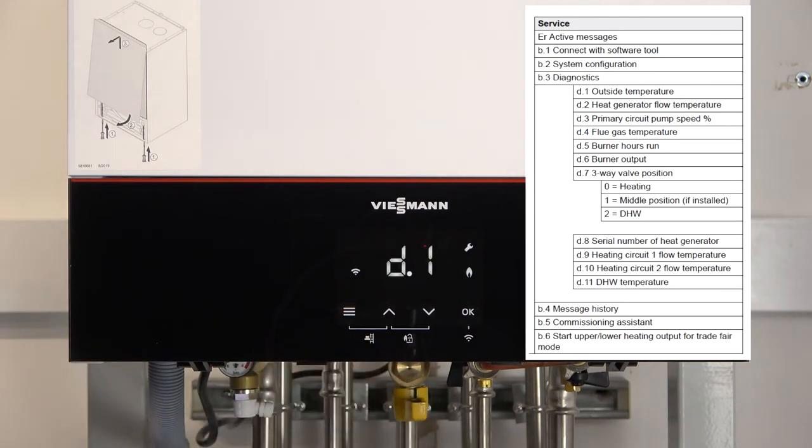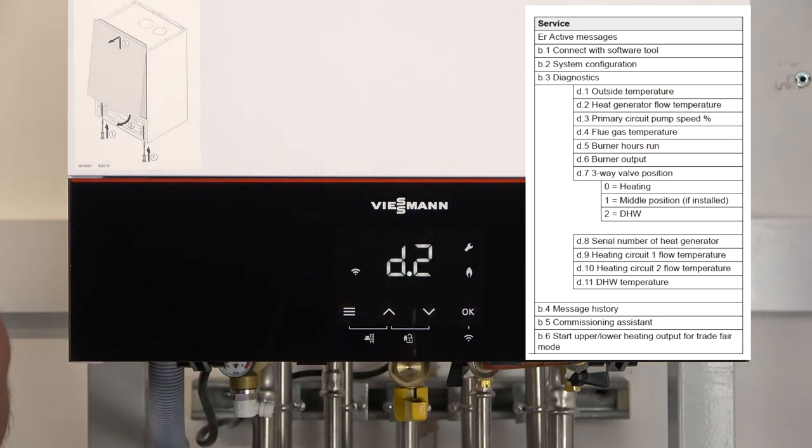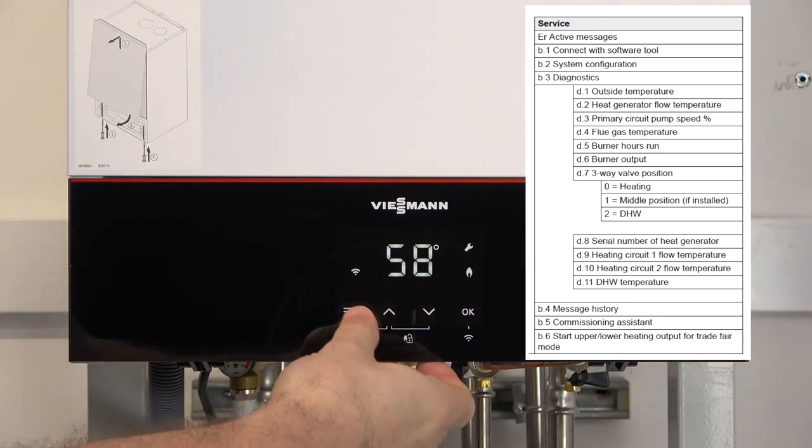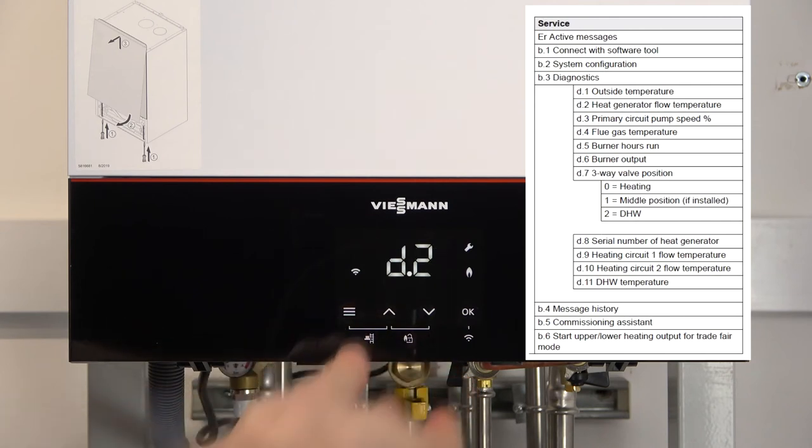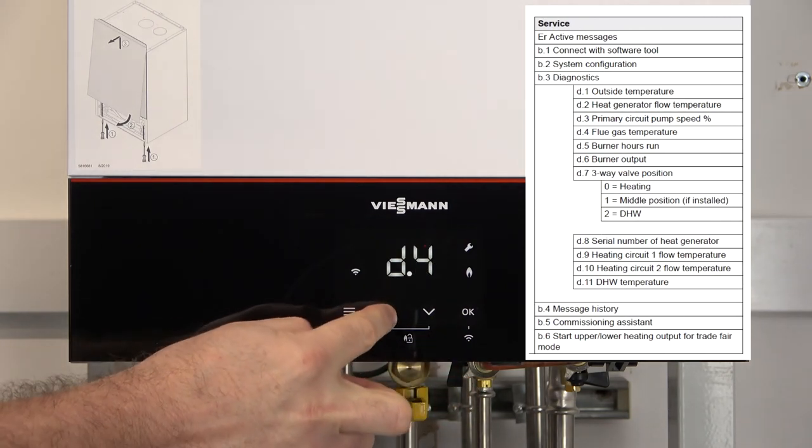To return back out of there, we press the menu button once to get back to the D codes. You can scroll through these now to check whichever parameter you want to see. So this one, for example, is the flow temperature within inside the boiler. So press OK. We can see there this boiler is actually at 57 degrees currently. There are other options in there, and to scroll through, come back out of the menu button and you can scroll through any of these that you'd like to check.